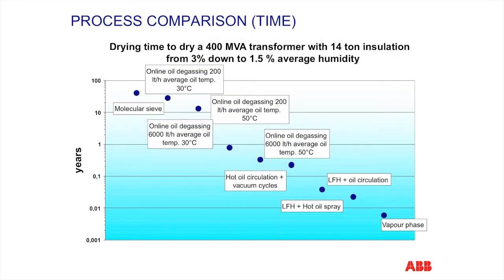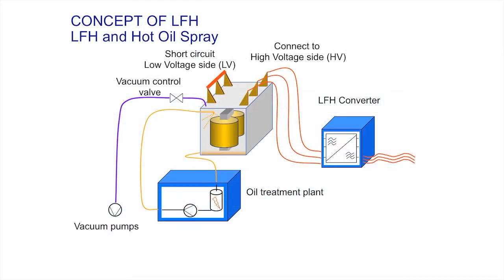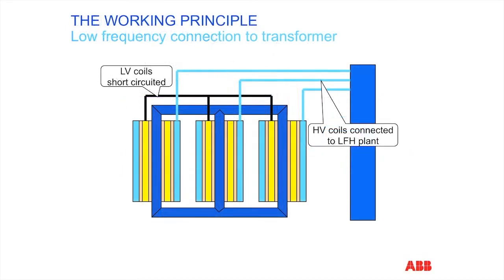In addition to the heating of the windings, vacuum is used to remove the water as it is driven from the cellulose insulation. A heated oil spray has a supporting function to heat insulation that is not in contact with the metal windings. A typical configuration of a low-frequency heating plant is shown here. As you can see, the low-voltage side is shorted out, and the LFH converter is connected to the high-voltage side of the transformer. A vacuum system is also connected to the transformer, as well as an oil heating and recirculation system. The moisture content in the vacuum stream is measured to calculate the total amount of water removed from the transformer. If only a DC voltage was applied to the high-voltage windings, then no induced current would flow in the low-voltage windings. Even frequencies of less than 1 Hz will induce current flow and facilitate the heating process.